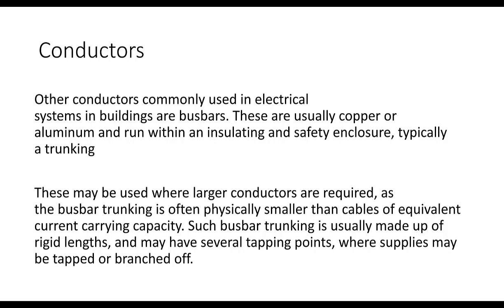Other commonly used electrical systems seen all over art and architecture buildings are called bus bars. These are usually copper or aluminum and run within an insulating and safety enclosure, typically called a trunking. We'll see these overhead on the third floor and also in the fab lab, which has high electrical consumption. Bus bar trunkings are used where larger conductors are required, and they're often physically smaller than cables of equivalent current carrying capacity, so it's both size and efficiency that drives their use. They're usually made up of rigid lengths and have several tapping points, which are connecting points for further distribution of electricity.